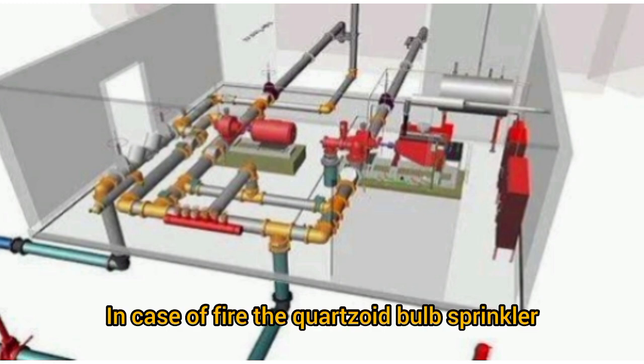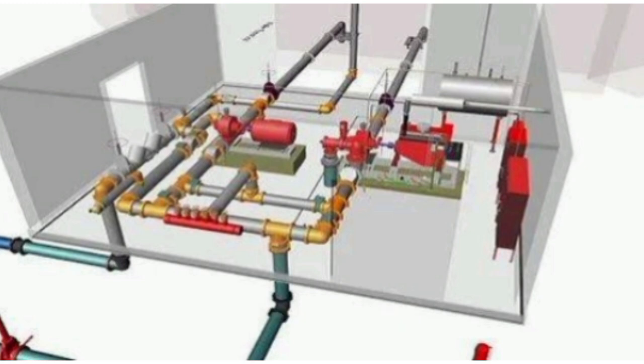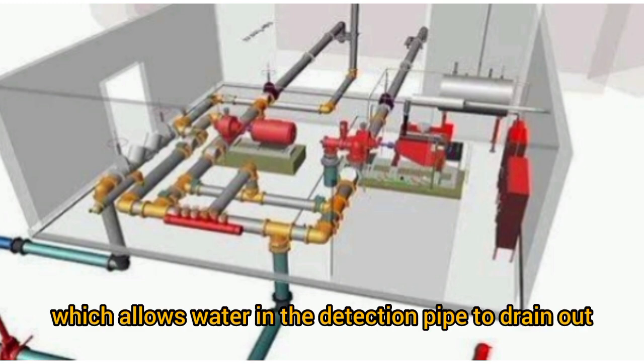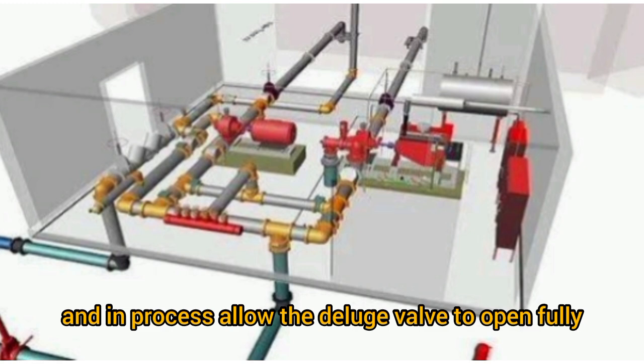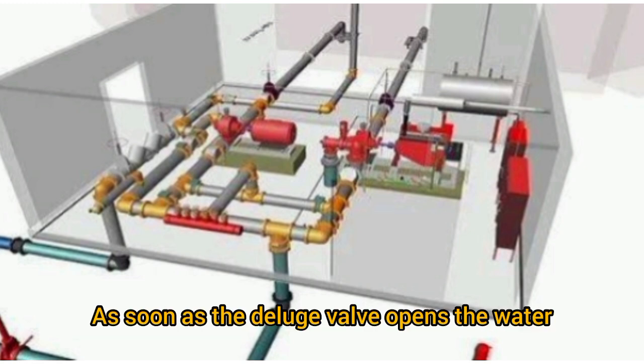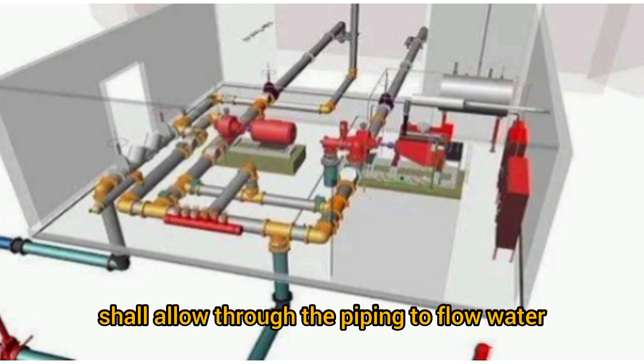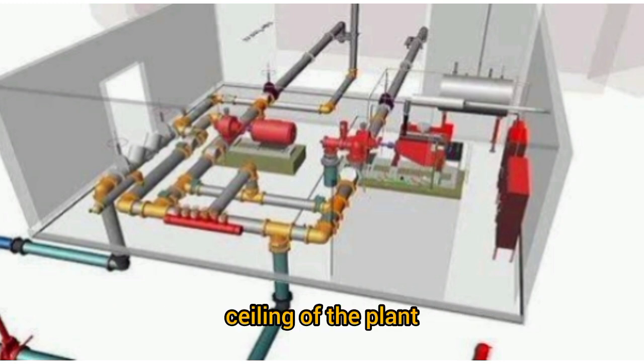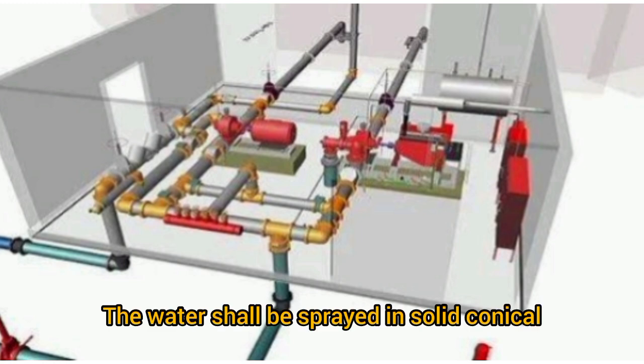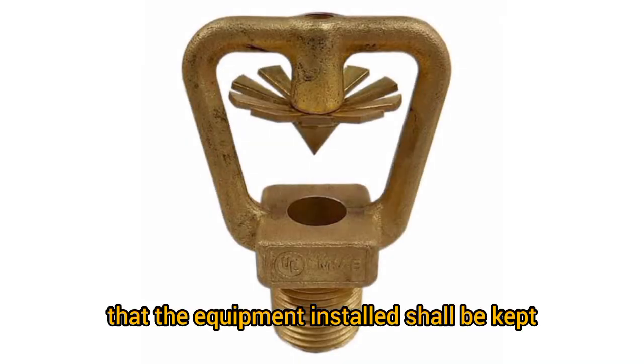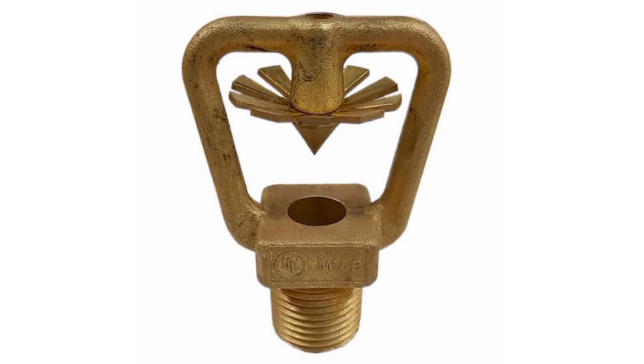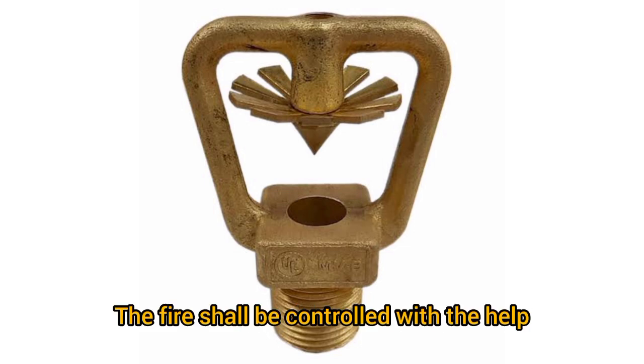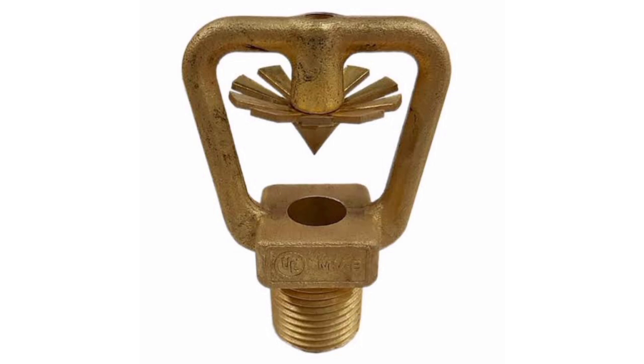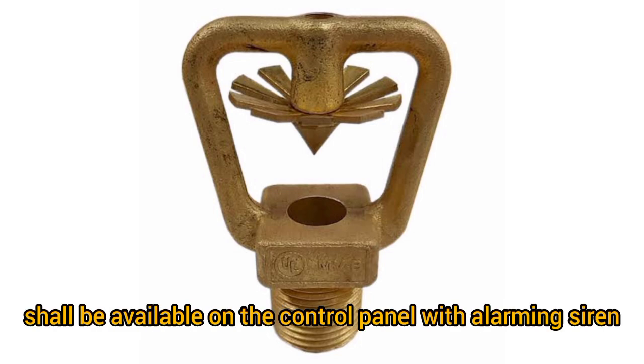Operation: in case of fire, the quartzoid bulb sprinkler shall burst due to heat, which allows water in the detection pipe to drain out and in the process allows the deluge valve to open fully. As soon as the deluge valve opens, the water shall flow through the piping to all water spray nozzles mounted on the ceiling of the plant. The water shall be sprayed in a solid conical spray pattern to cover the entire area of the plant floor so that the equipment installed shall be kept cool to avoid heat radiation and further ignition of fire. The fire shall be controlled with the help of the water spray system. The indication of operation of the system shall be available on the control panel with alarming siren.